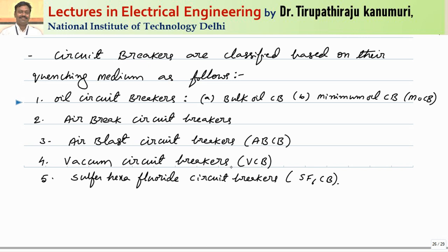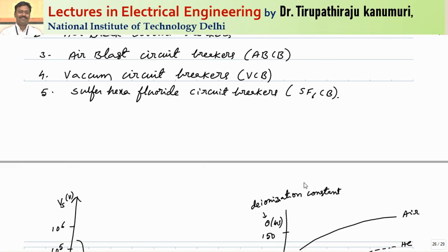The next type is the sulfur hexafluoride SF6 circuit breaker. SF6 is an electronegative gas — it will absorb electrons. The main reason for arc production is electrons, since positive ions have more weight and cannot contribute significantly to current carrying. So the major contribution is from electrons. If the electrons can be absorbed, the dielectric strength of the medium increases drastically. That is why SF6 can also be used as a circuit breaker medium.